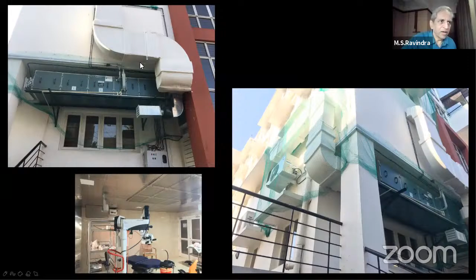there is a negative pressure around the patient's face, so it goes into the return ducts. The air exchanges we have increased, and the positive pressure inside the operation theater we have reduced. The air comes out from the OT here, gets filtered through the AHU, then gets cooled and goes back inside the OT. There is a cycle of about 32 air changes, and the air percolates down from here. We have fixed a UV light, so whatever air comes down also gets sterilized by UV light.